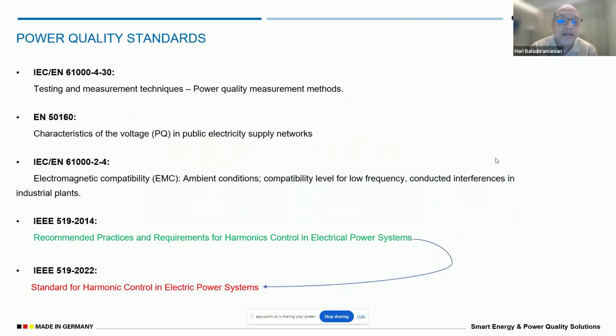61000-4-30, which is testing and measurement techniques for power quality measurement methods. EN 50160, which is the characteristics of the public distribution voltage. 61000-2-4, which is EMC compatibility of all the industrial plants and the equipment they are using. And very interestingly, the most talked about standard, IEEE 519: earlier, in 2014, it was called recommended practices and requirements for harmonic control in electrical power systems. Now they have come back and said no, it is no more a guideline, we call it a standard for harmonic control in electric power systems.